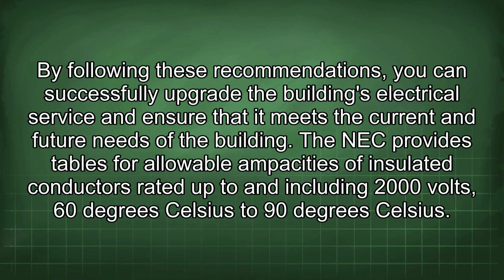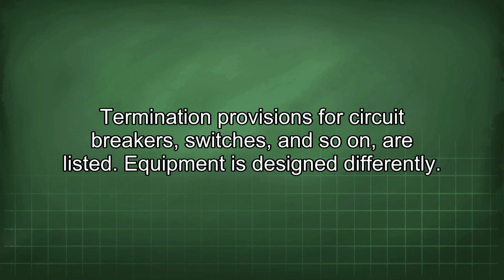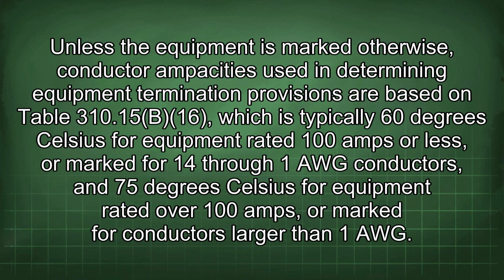The NEC provides tables for allowable ampacities of insulated conductors rated up to and including 2000 volts, 60 degrees Celsius to 90 degrees Celsius. Termination provisions for circuit breakers, switches, and so on are listed. Equipment is designed differently. Unless the equipment is marked otherwise, conductor ampacities used in determining equipment termination provisions are based on Table 310.15(B)(16), which is typically 60 degrees Celsius for equipment rated 100 amps or less, or marked for 14 to 1 AWG conductors, and 75 degrees Celsius for equipment rated over 100 amps, or marked for conductors larger than 1 AWG.